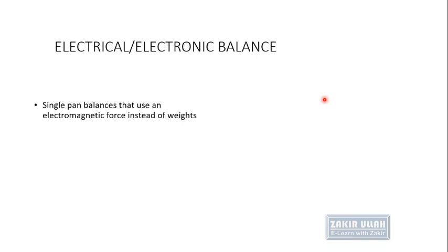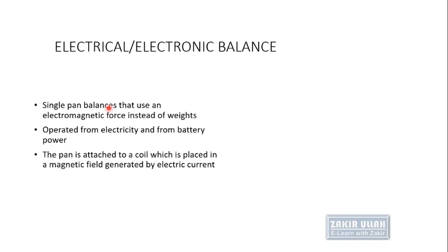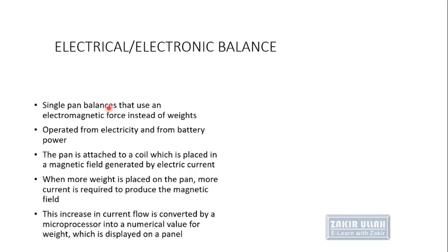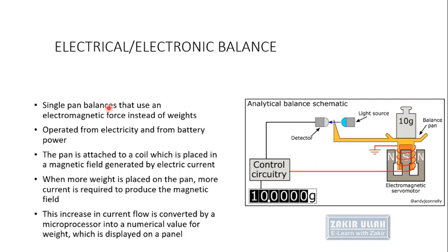The different types of electrical or electronic balances mostly have a single pan that uses electromagnetic force instead of weights, operated with electricity or battery power. The pan is attached to a coil placed in a magnetic field generated by electric current. When weight is placed on the pan, an electromagnetic field is generated; more weight produces a stronger field. The increase in current flow is converted by a microprocessor installed inside the electronic balance, and it gives a numerical value of the weight displayed on the panel.